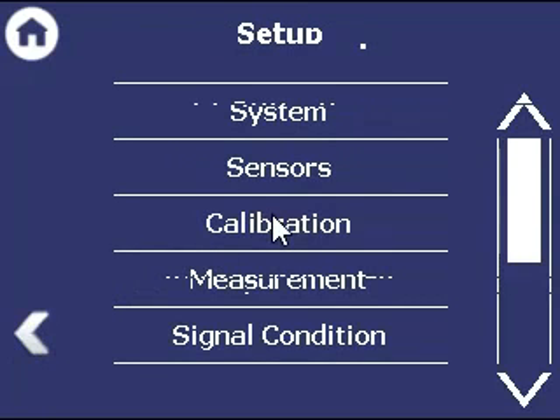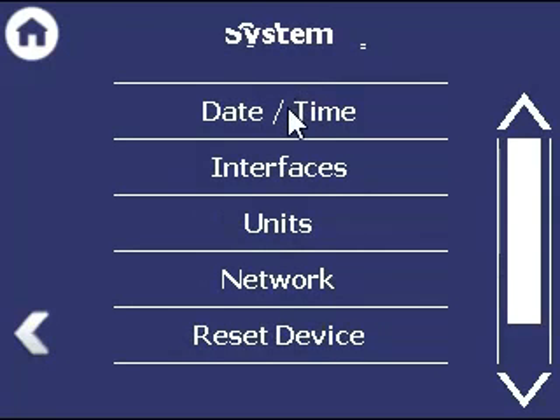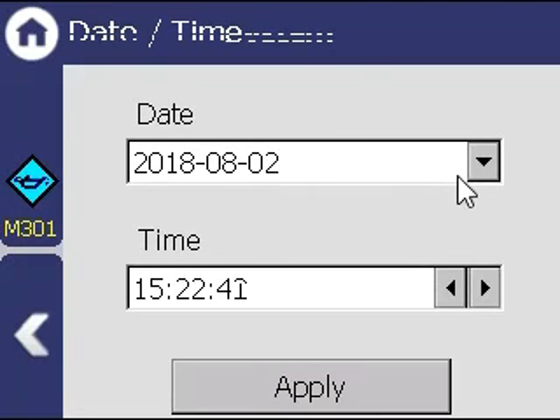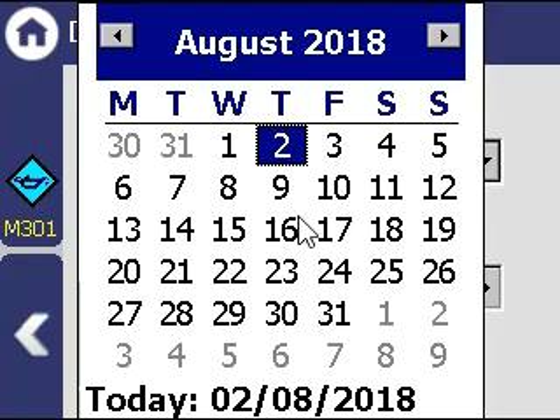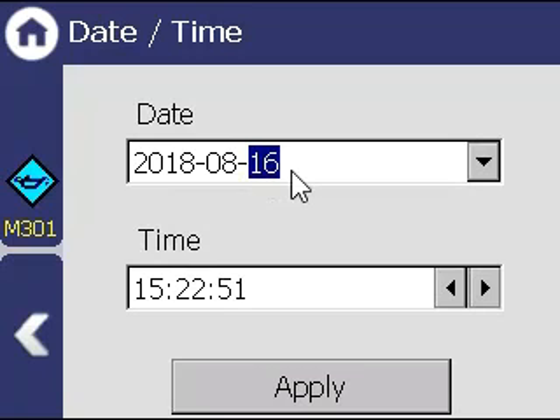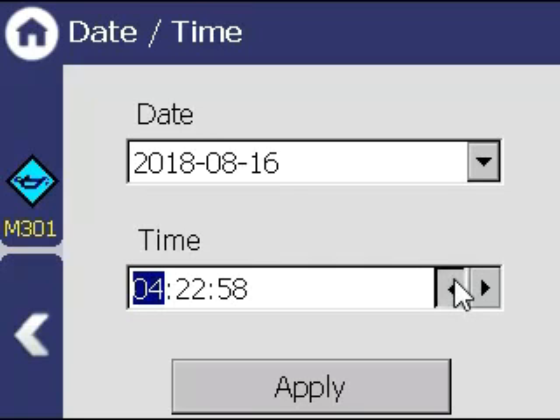Setup, system, date, time. Here we can make the proper adjustments to our date by selecting the drop-down menu and finding the correct setting. The time can be adjusted by selecting the incorrect field and making the corrections with the arrows to the right. The LB470 will automatically adjust your calibration every day based on the decay of the source for that day. So selecting the proper date, time, and isotope, more on the isotope later, has an impact on the continued accuracy of your gauge. Click Apply, then Back.